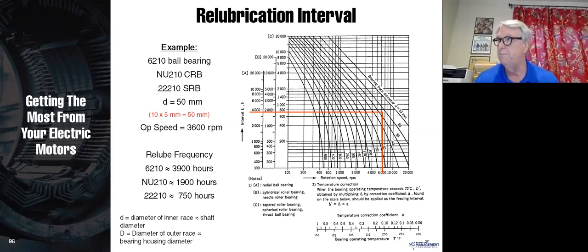All right, let's go through a couple questions here. The first that we see is, is the last 2 number calculation for bearing ID a standard for all bearing manufacturers? Yeah, that tends to be a standard for all bearing manufacturers, at least NEMA bearing manufacturers. Now, I can't say from around the world, but for your smaller bearings, this doesn't work if you've got a 10,000 horsepower motor. But for your smaller bearings, this is pretty standard amongst all the manufacturers, and this is a bearing thing more than it is a motor manufacturer thing, and the bearing manufacturers do adhere to that.